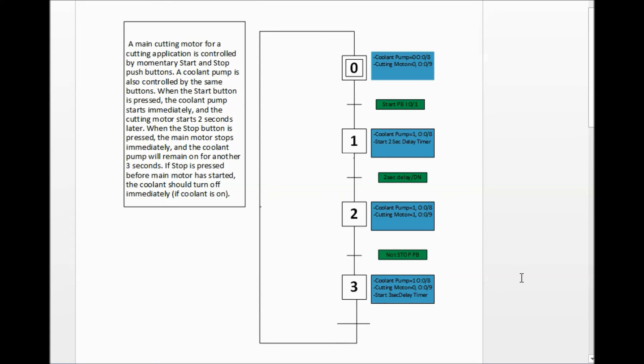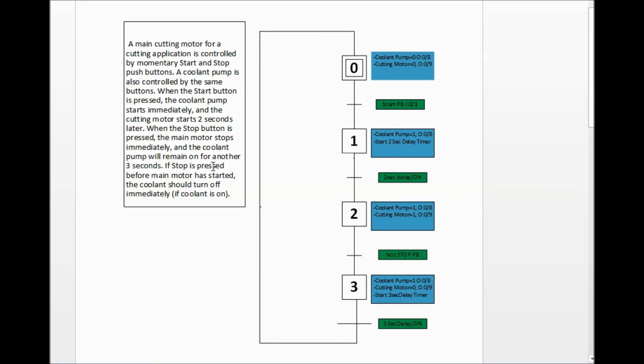At step 3, the coolant pump stays on at O:0/8, the cutting motor is set to 0 (off) at O:0/9, and we start a three-second delay timer. When the three-second timer completes, we go back to step 0, which sets the coolant pump to 0 — no longer on. There's one more thing to consider: if stop is pressed before the main motor has started, the coolant should turn off immediately.